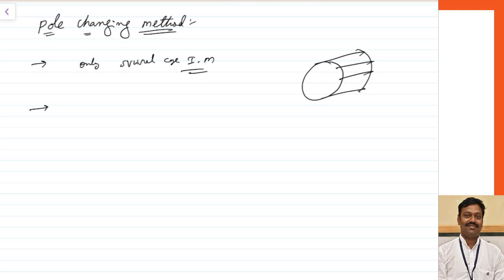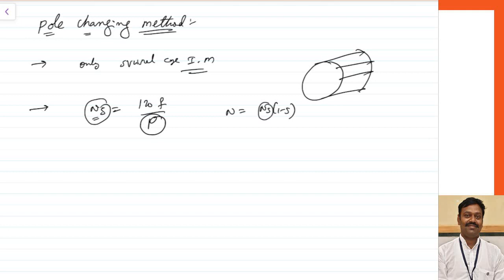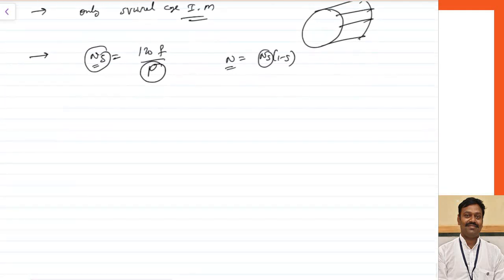In this method, we control speed by changing the number of poles. We know Ns = 120F/P, so by changing the number of poles I am going to change my synchronous speed. When the synchronous speed is changed, since N = Ns(1 - S), as Ns is changed, N will also be changed. This is the basic technique.